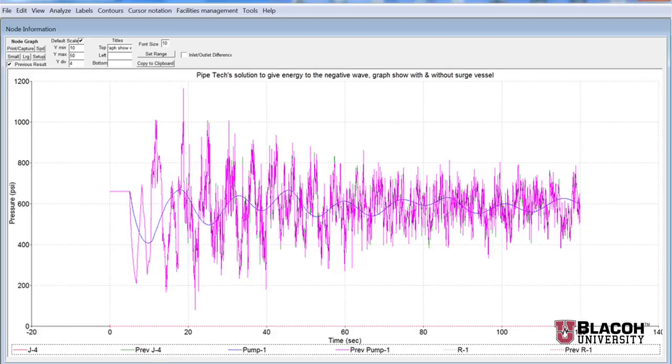In this case, it would keep the piping within the maximum operating pressure of the system. If you're looking at 300-pound class ANSI flanges, piping that's rated to 720 PSI, we're dealing with a system that meets the ANSI requirement and the pressure rating of the pipe or far exceeds that.